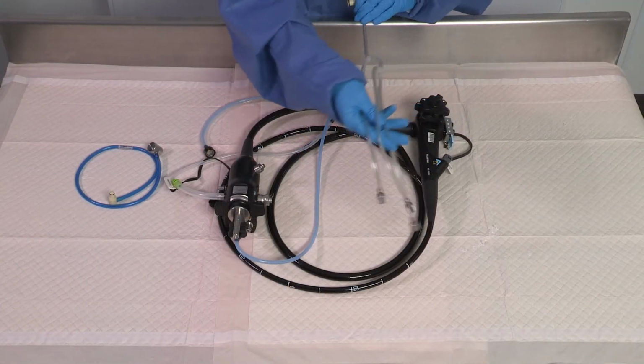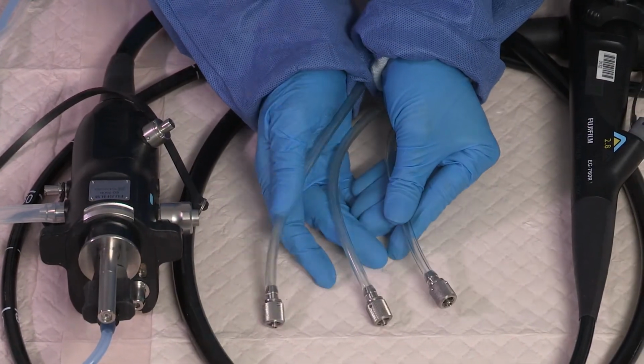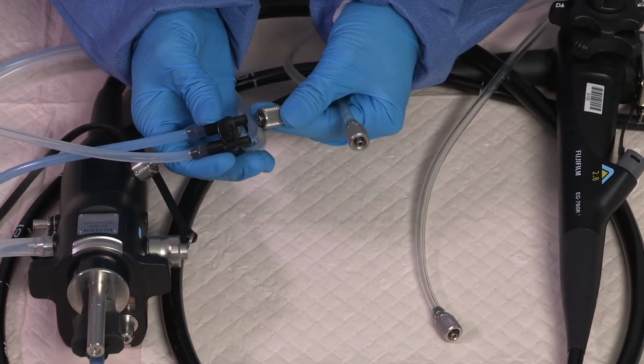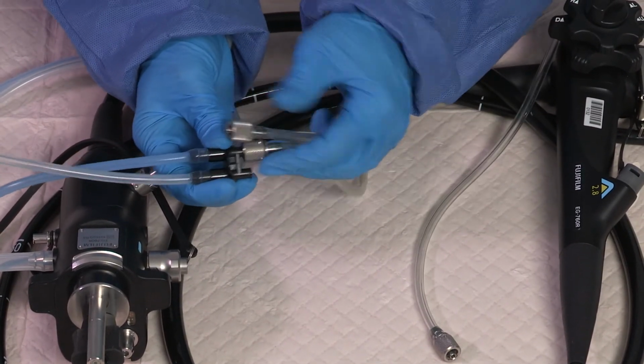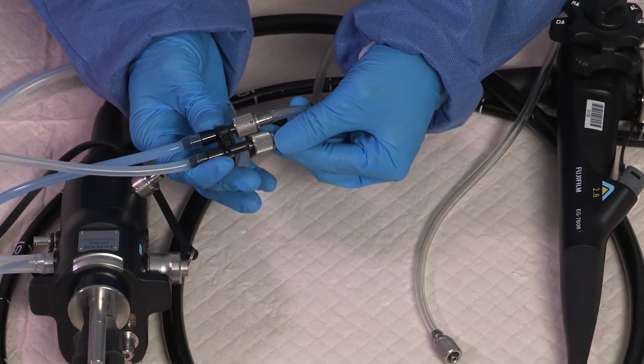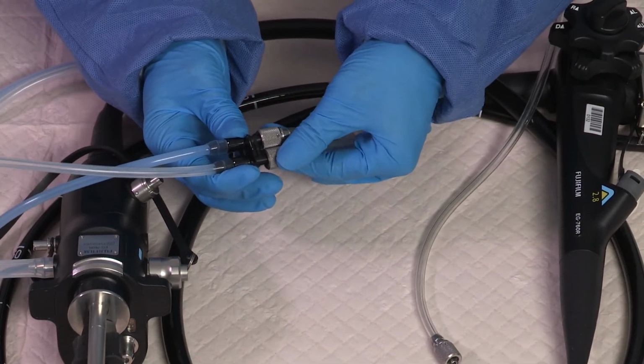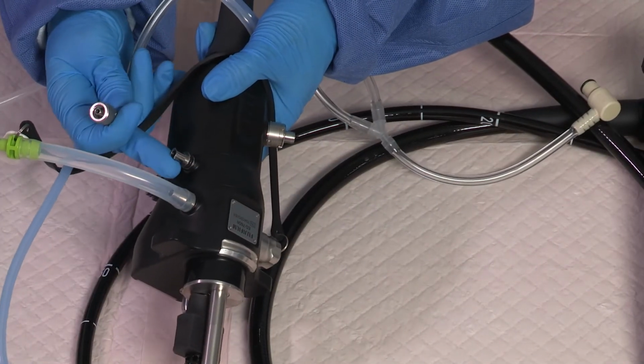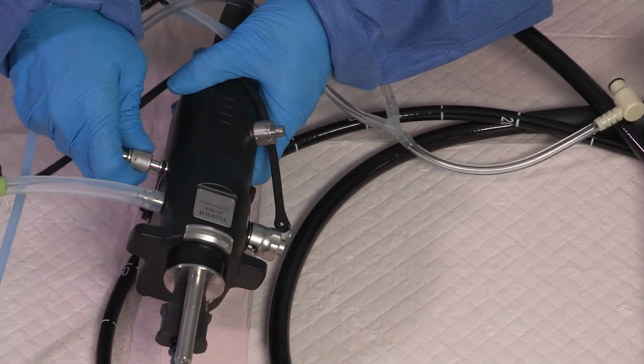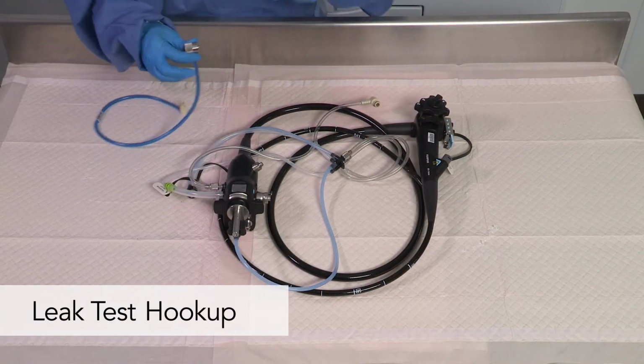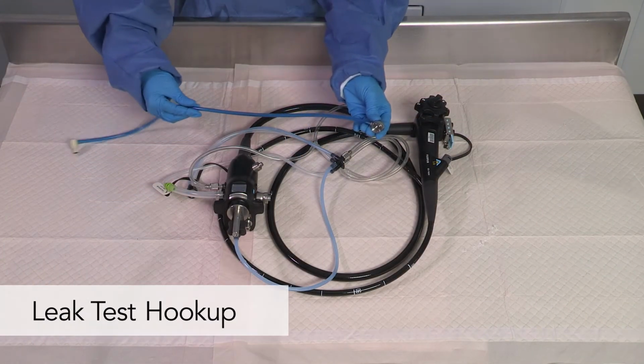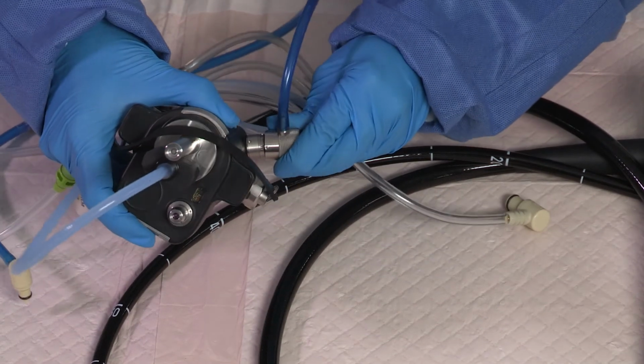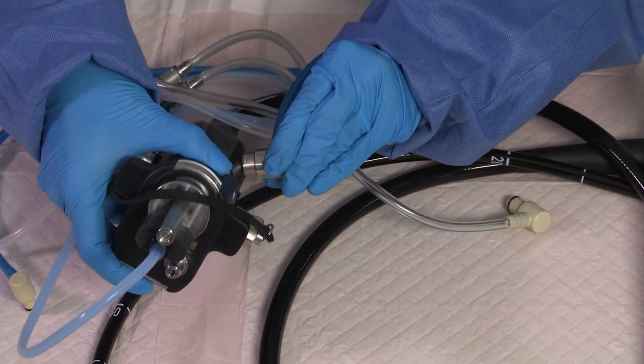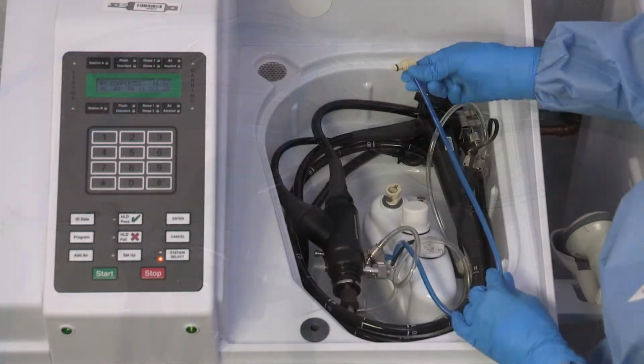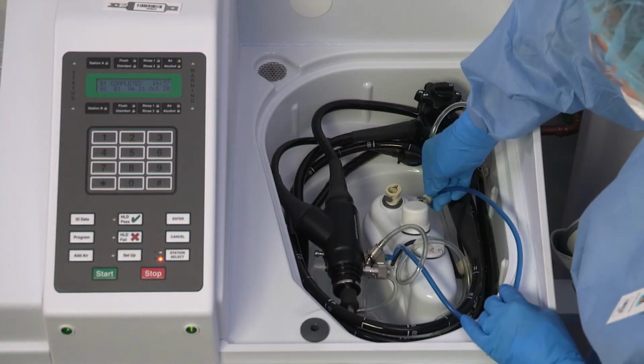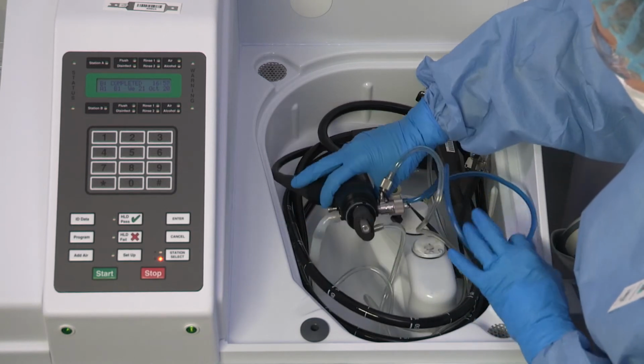The DSD hookup consists of 3 luer connectors. Attach 2 of the luer connectors to the 2 syringe ports on the Fujifilm injection tube. The 3rd luer connector attaches to the endoscope's water jet inlet. To connect the Fujifilm DSD leak test hookup, align the slot on the hookup with the endoscope's venting connector. Push on and turn clockwise to engage. Connect the hookup to the basin's leak test connector. Always refer to the provided hookup IFU.